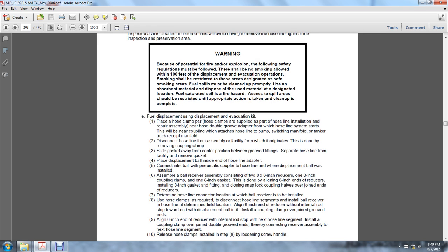E. Fuel displacement using the displacement and evacuation kit. Place a hose clamp, supplied as part of the hose line installation and repair assembly, near the hose double groove adapter where the hose line system starts. This will be near the coupling attaching the hose line to the pump or switch manifold, or the tanker truck's receipt manifold. Disconnect the hose line from the facility from which it originates. This is done by removing the coupling clamp and sliding the gasket away from the center position between the groove fittings. Separate the hose lines from the facility.